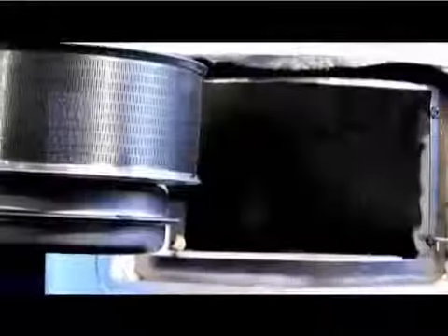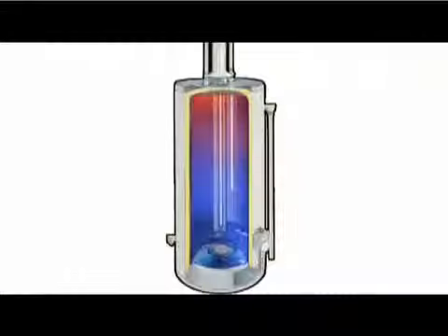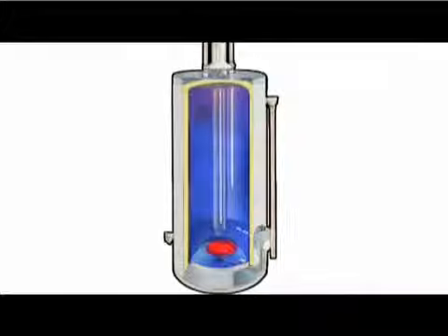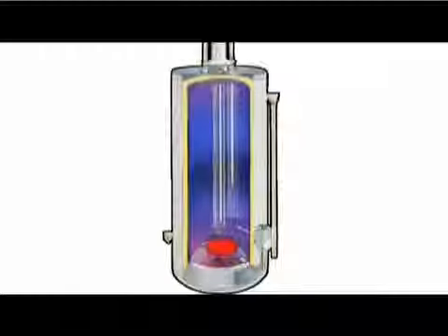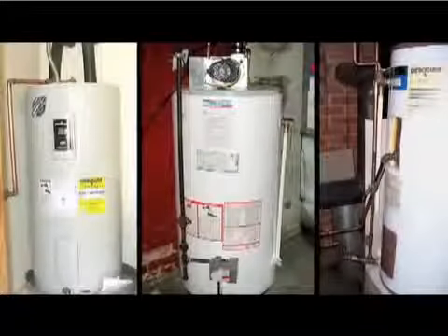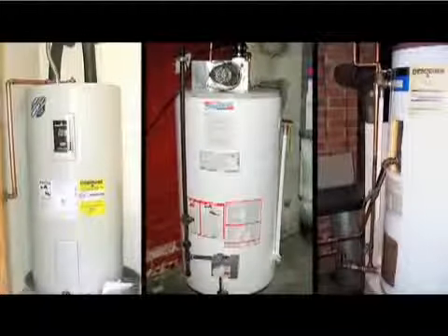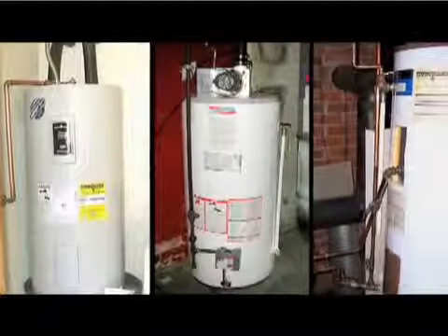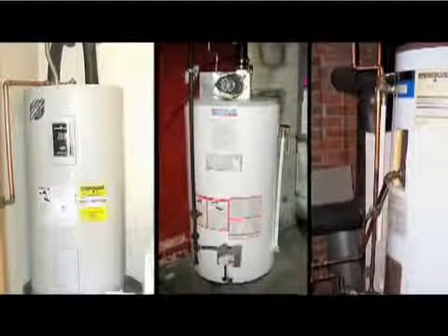A separate chamber below the main tank contains the unit's heating element, which is controlled by a thermostat, or for natural gas and propane units, a burner control. As the hot water in the tank is exhausted, the burner below ignites to heat incoming fresh water. Little or no hot water is available during this recovery time. Storage water heaters provide a relatively low installed cost, a variety of sizes to serve large and small homes, and respectable flow rates to deliver domestic hot water.